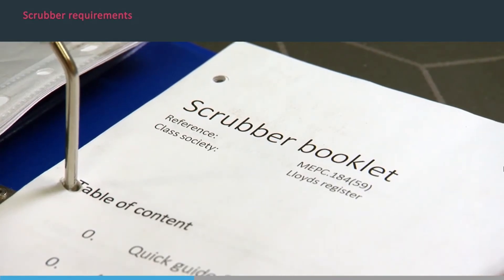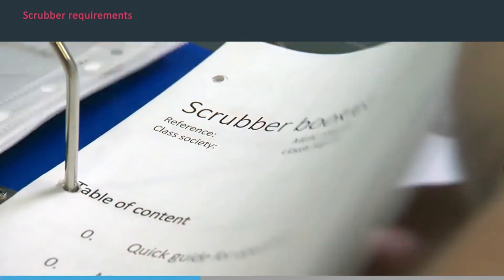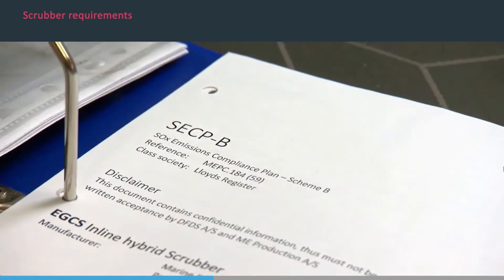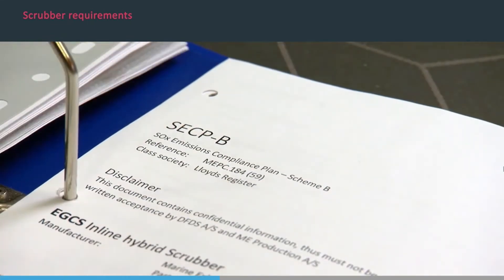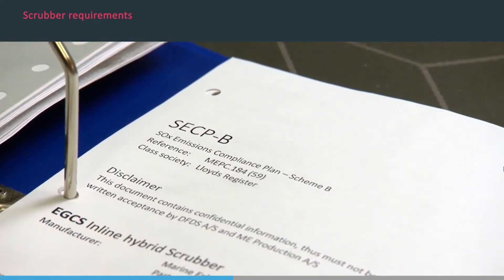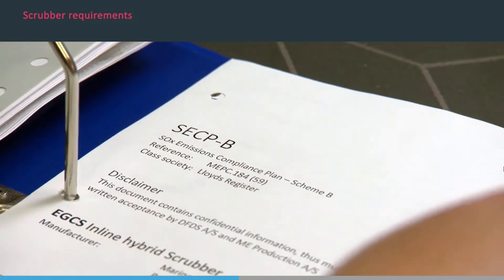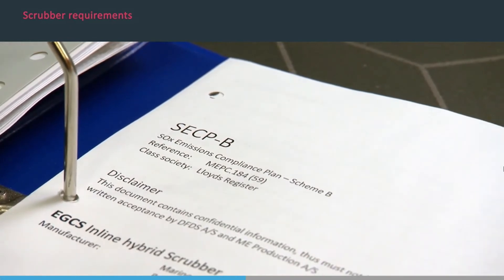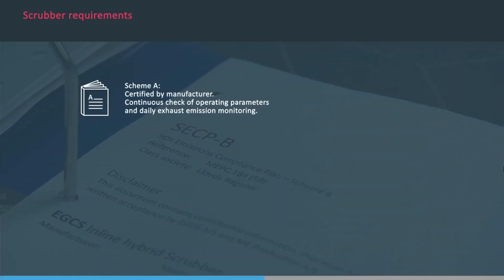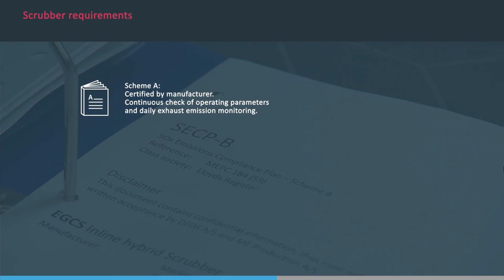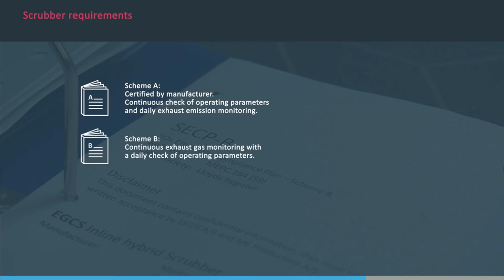Scrubbers must have an exhaust gas cleaning system, EGCS, technical manual, ETM, and there are two ways by which they are certified. Scheme A, certified by the manufacturer, known as ETM-A, based on initial emission performance unit certification, together with a continuous check of operating parameters and daily exhaust emission monitoring.